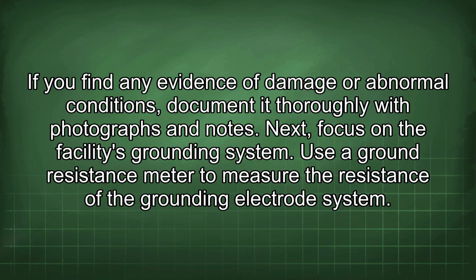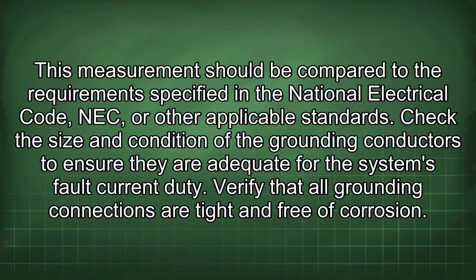Next, focus on the facility's grounding system. Use a ground resistance meter to measure the resistance of the grounding electrode system. This measurement should be compared to the requirements specified in the National Electrical Code, NEC, or other applicable standards. Check the size and condition of the grounding conductors to ensure they are adequate for the system's fault current duty. Verify that all grounding connections are tight and free of corrosion.